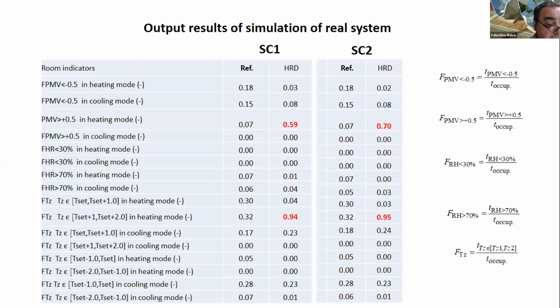This is also observed by the fact that, when using the heat recovery device, the indoor temperature is 2 degrees Celsius above the set point 90% of the time of the heating period. It means that if the set point is 20 degrees, in this heating period the air temperature of the zone is between 21 and 22 in 90% of the heating period.